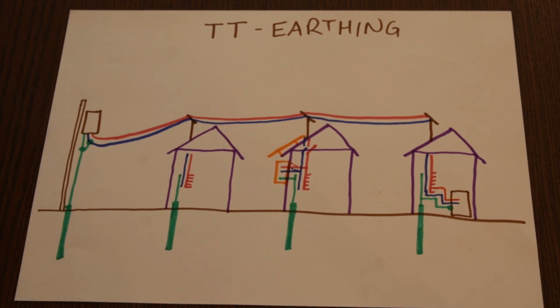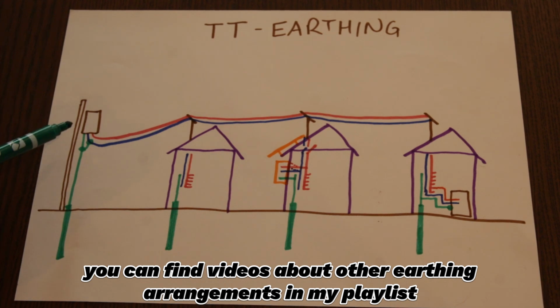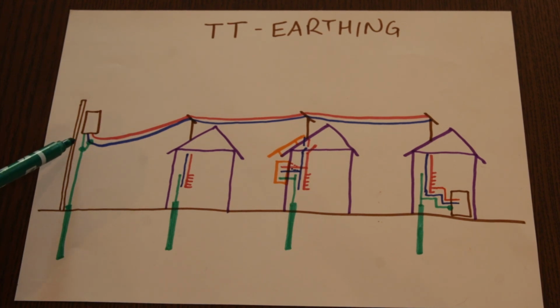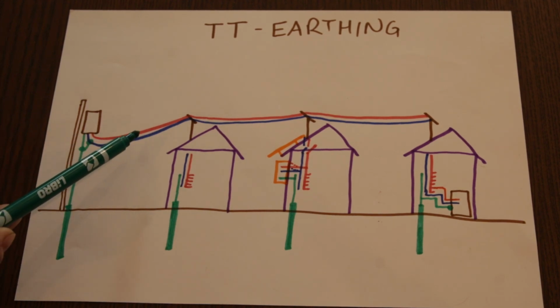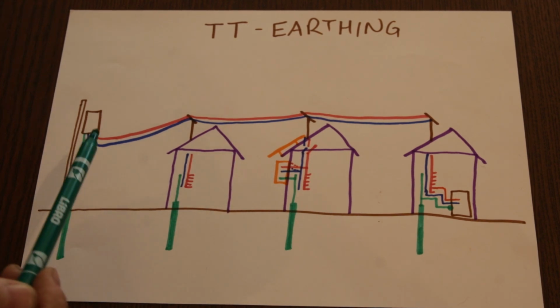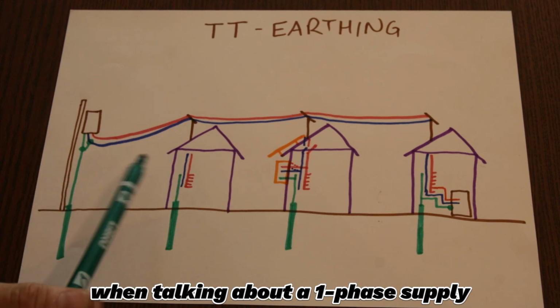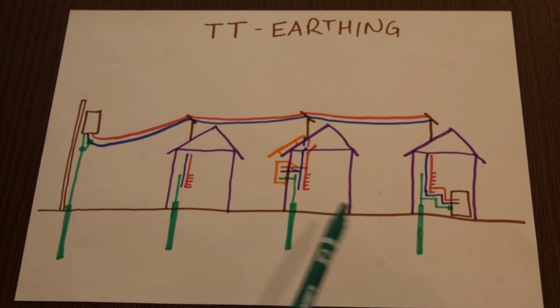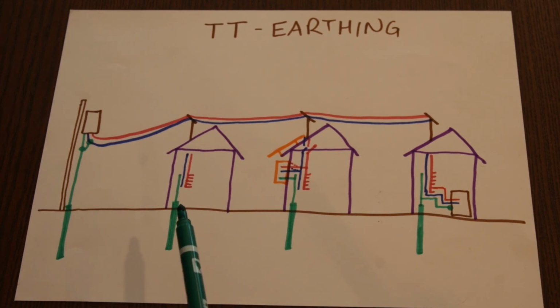So in the TT earthing system we still have, similar to any TN earthing, a transformer which does have, of course, grounding, and it does have a connection, a bond between its grounding and the neutral. This provides the definition of the neutral wire, makes it zero potential, while all other outputs of the transformer are then phase wires. But then from the transformer there is only a 2-wire configuration to every one of the users, which are symbolized here as 3 houses. Now comes the difference to a TN system like a TN-C or TN-S.